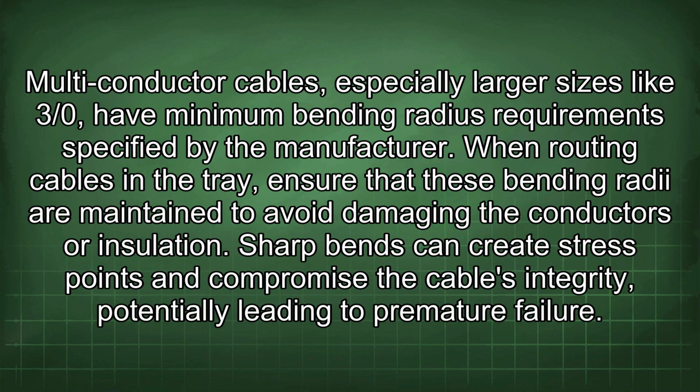Multi-conductor cables, especially larger sizes like 3/0, have minimum bending radius requirements specified by the manufacturer. When routing cables in the tray, ensure that these bending radii are maintained to avoid damaging the conductors or insulation. Sharp bends can create stress points and compromise the cable's integrity, potentially leading to premature failure.